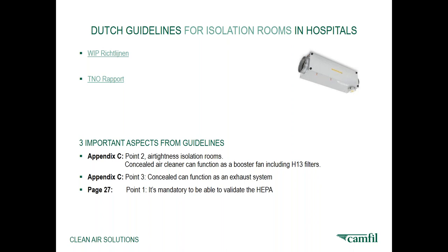Appendix C, point three: Conceal can function as an exhaust system because we're able to control the amount of airflow. It's mandatory to filter the outgoing air with an H13 filter, which is standard in our units. On page 27, point one, it's mandatory to be able to validate the HEPA filters. That is no problem for our Conceal unit either.